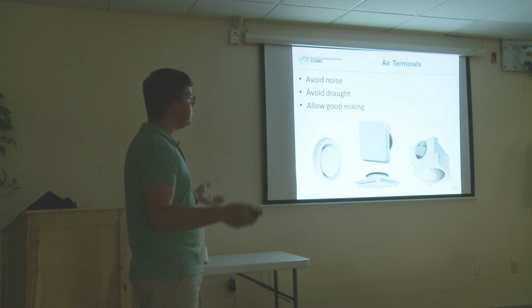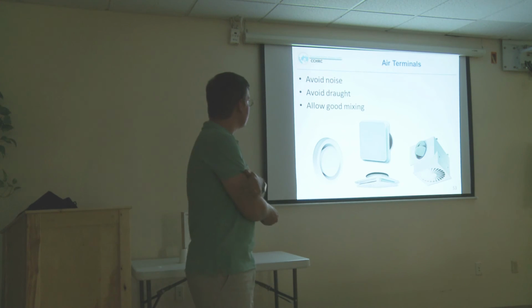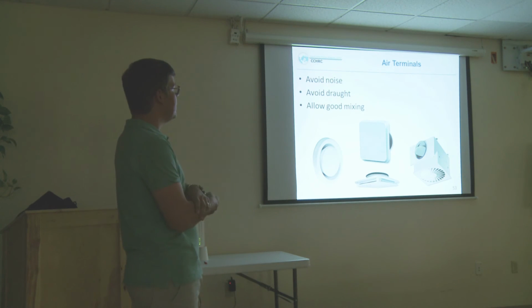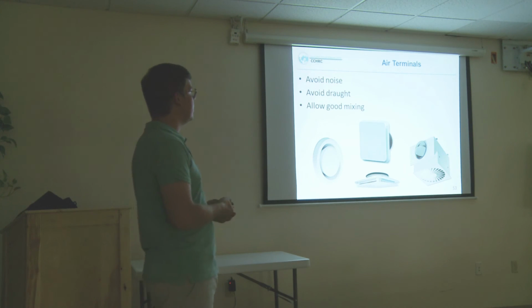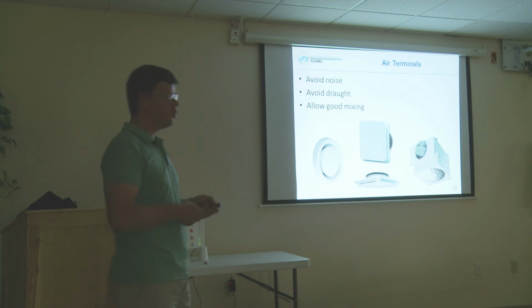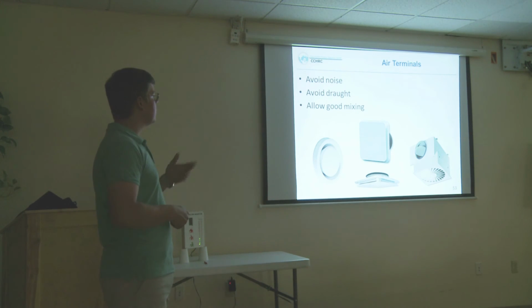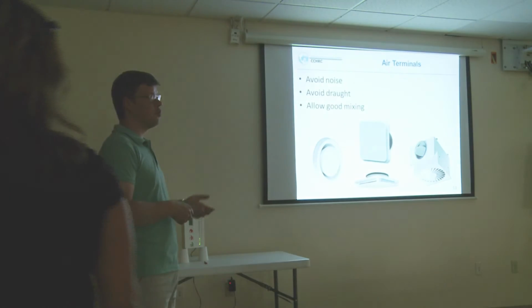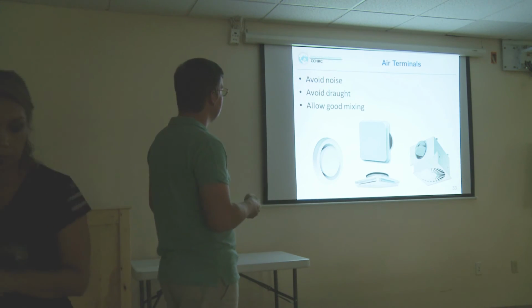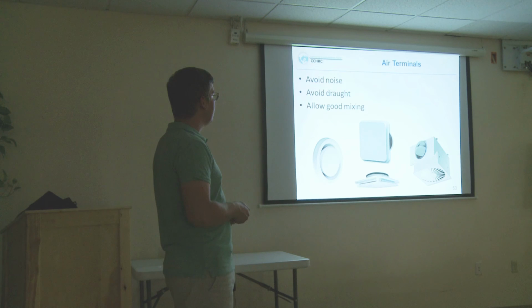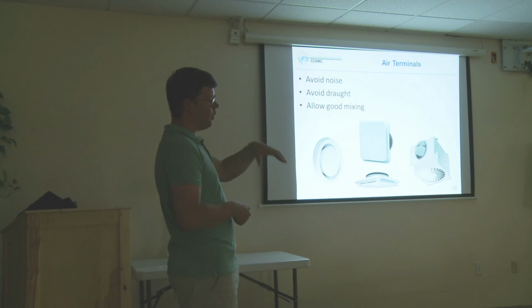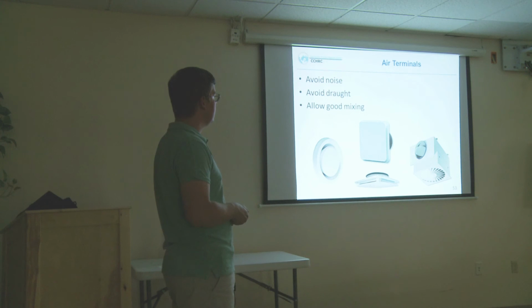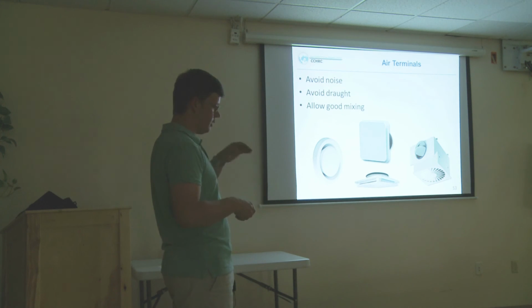Besides ventilation units, which are of course the heart of the ventilation system, we also have air terminals. They are somehow also a cause of trouble, because if chosen improperly, they might cause noise issues or draft issues. So it's very important to choose the right terminals, especially when placing the supply in a bedroom - it needs to be silent, and it needs to flow the air in a good direction so it doesn't blow on the sleeping people.